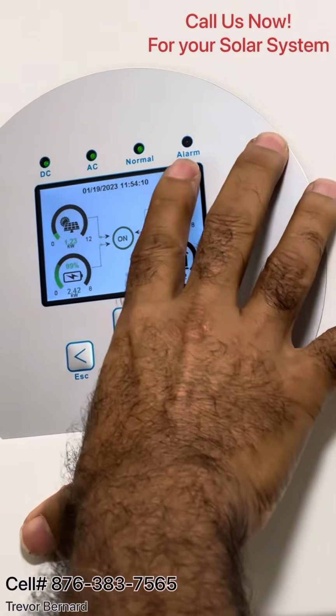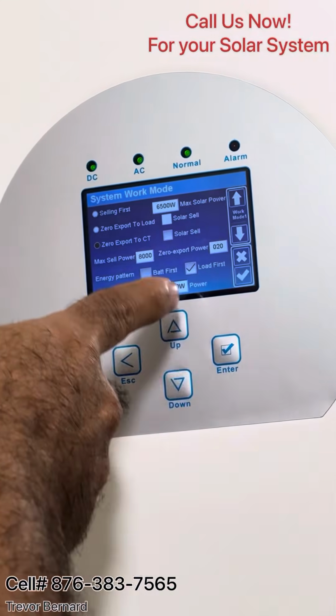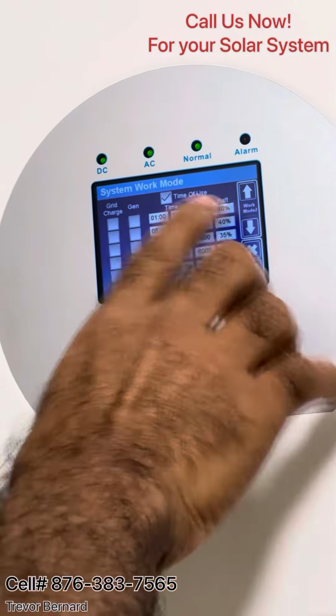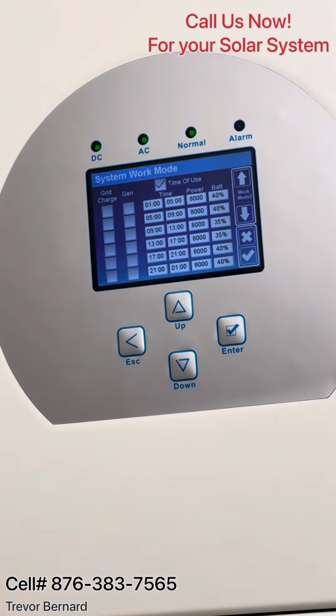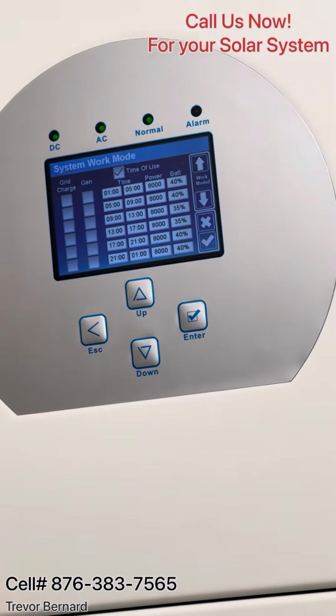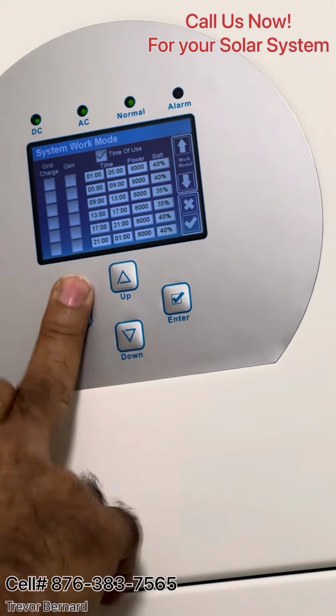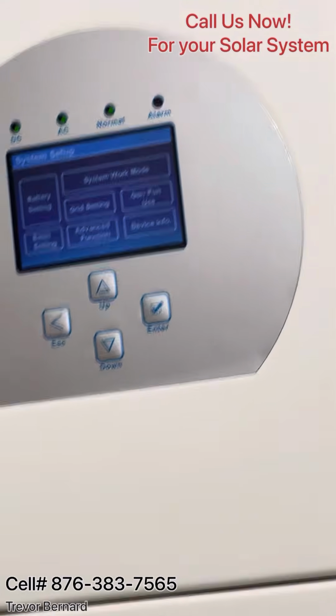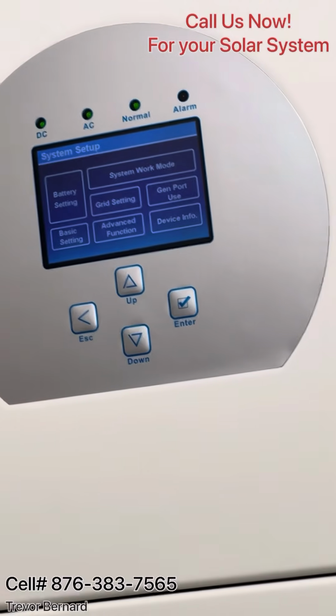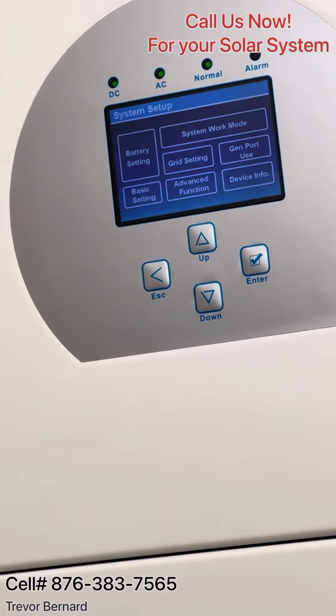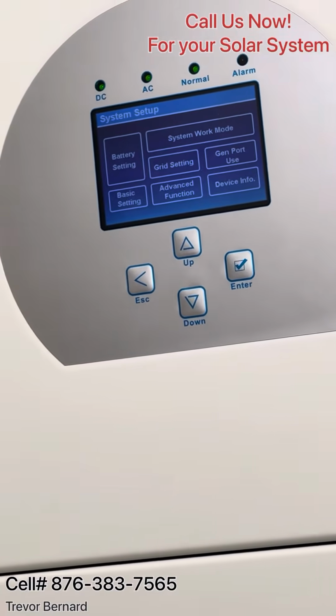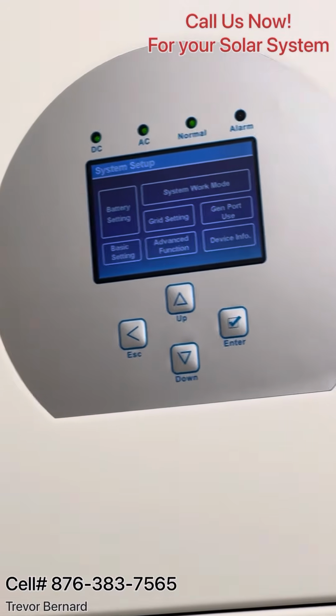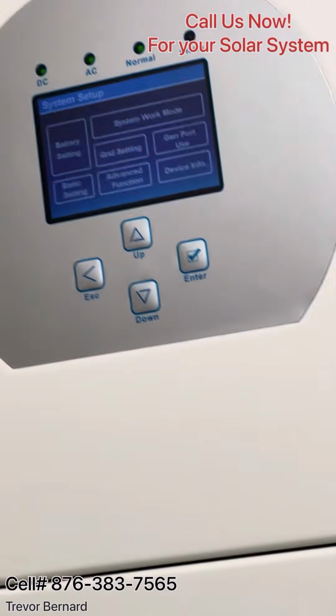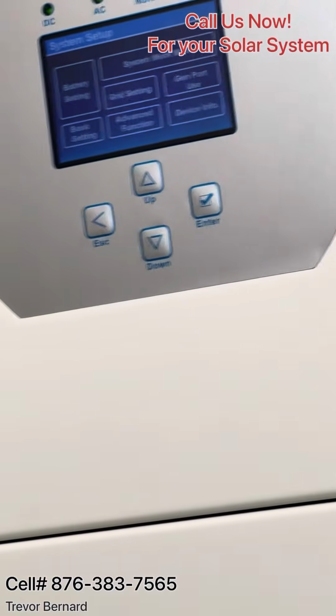Now, in that time of use, you can set this part here and change this at night. You might not want it to take the power from the battery, or if you do, you're always going to want to carry the battery down to even 30%. Did you set up the 20% for the battery? Yeah, he understands it, so I don't even have to interfere with it. So 20% is the lowest it can go. You don't want to discharge your battery below 20%.